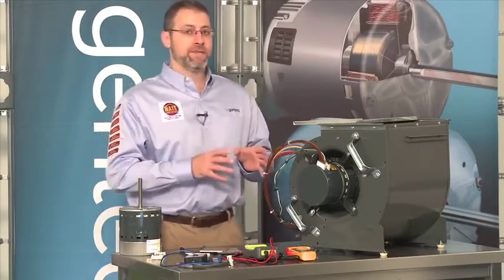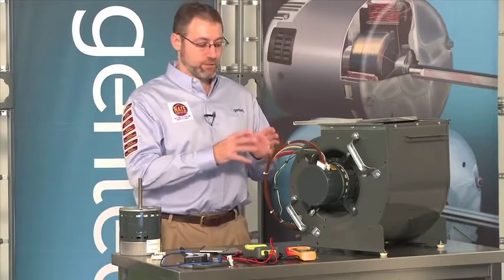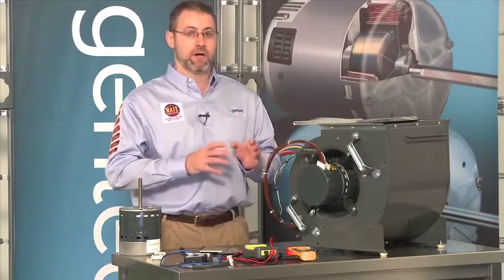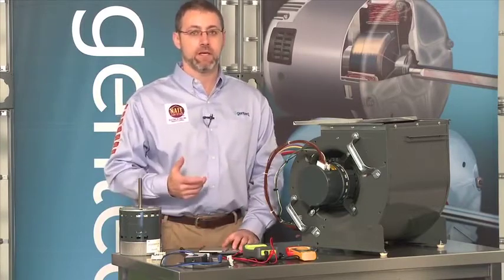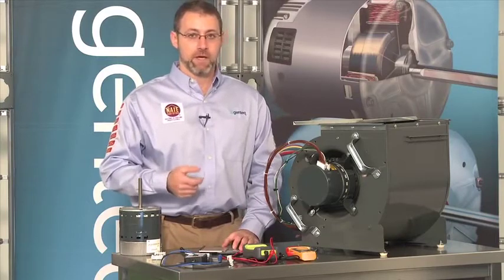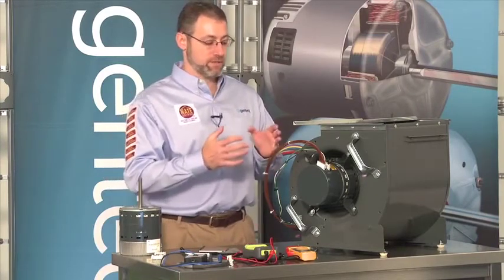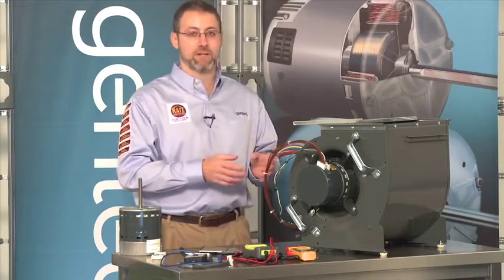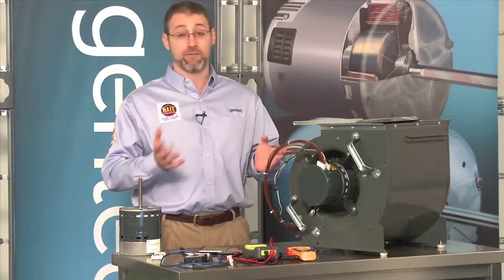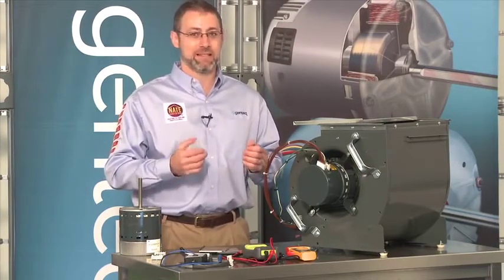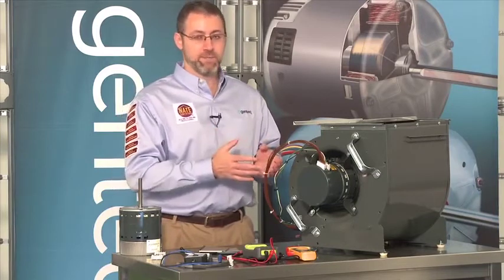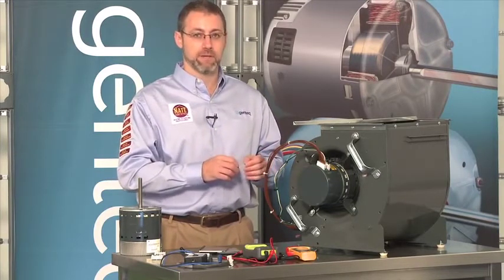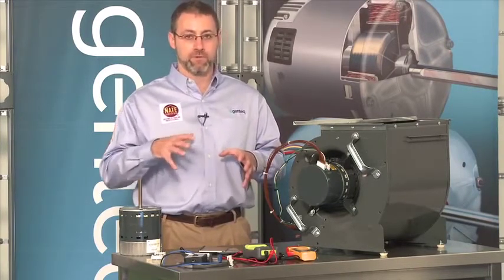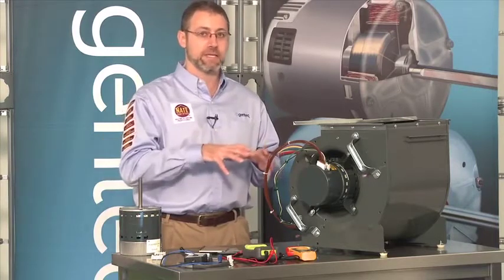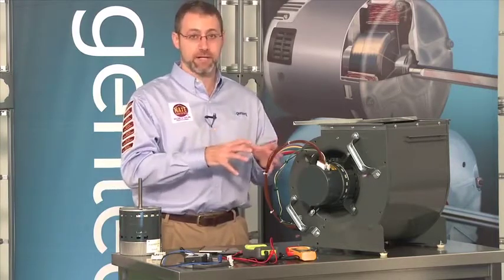So, one thing I want to talk about before we actually troubleshoot the motor itself is other issues you can have, primarily having to do with airflow. Many of us think that because this is a variable speed, constant airflow motor, I should just never have any airflow problems. And that's just not the case. The variable speed, constant airflow motor is speed limited, so it can only run so fast before we are going to limit the operation of the motor to protect the motor.